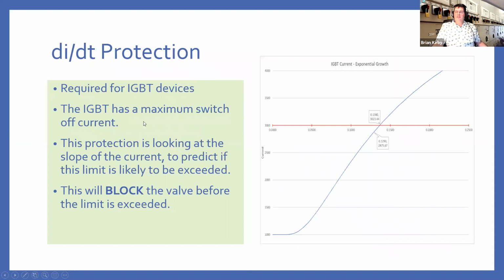A special case for DC protection is if you're running an IGBT for a VSC system. I mentioned you can turn them on and off, but IGBTs have a maximum switch off current.